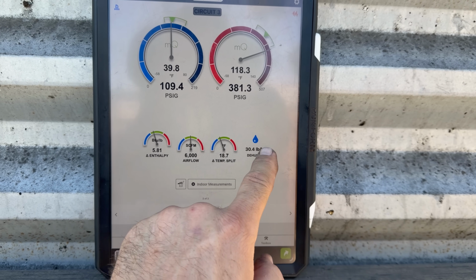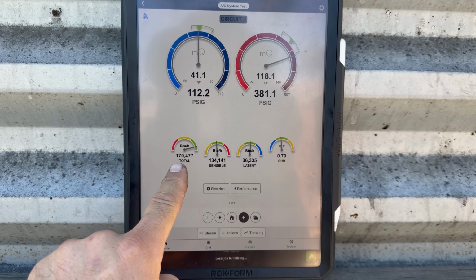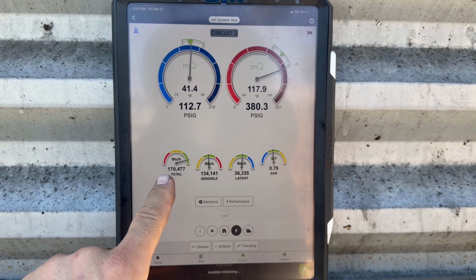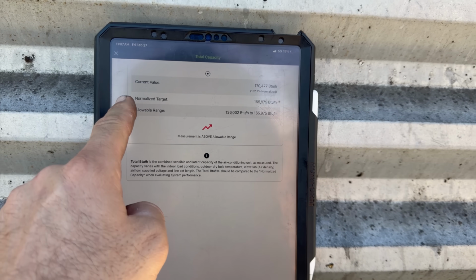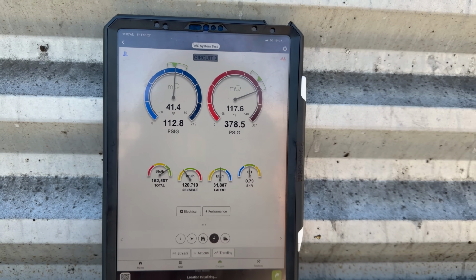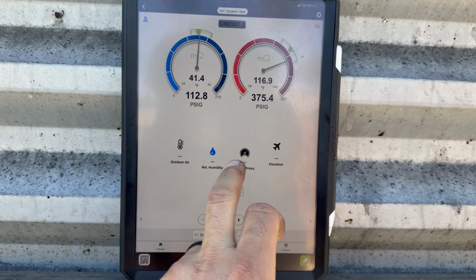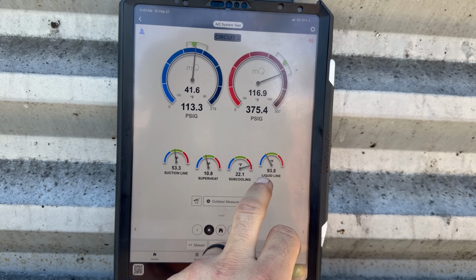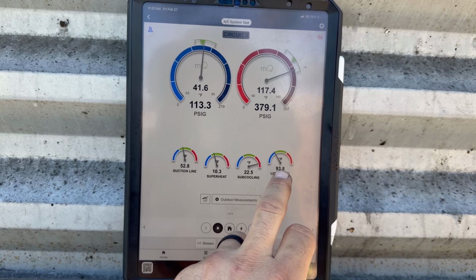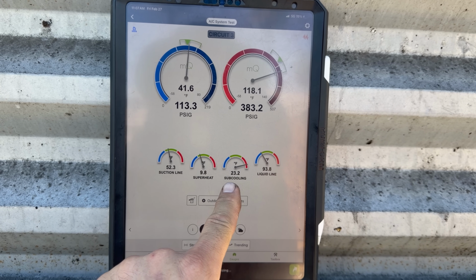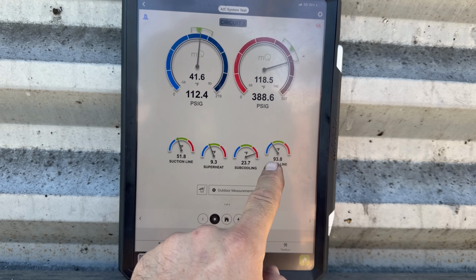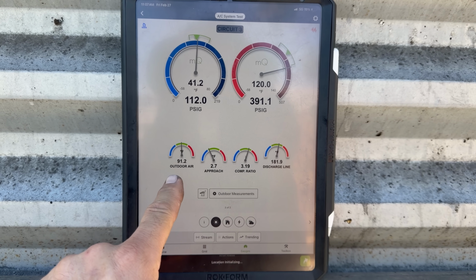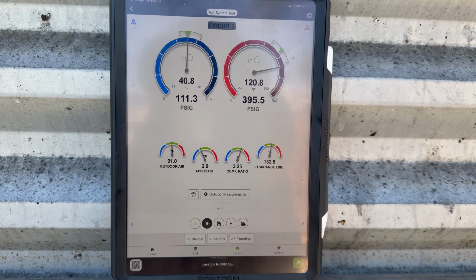Let's go to circuit 3 and let's look at delivered capacity. We're at 170,000 BTUs right now approximately, and normalized target is 165,000, so we seem to be pretty good on our delivered capacity. I'm not seeing any major problems with this guy. Okay, I don't like that the subcooling's a little bit higher on the third stage, but we can probably move our outside air temperature probe a little bit and that subcooling number will change.